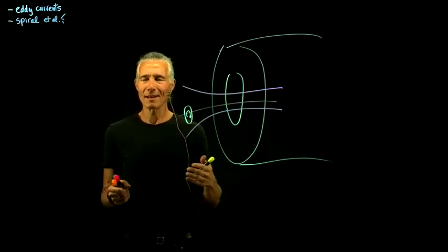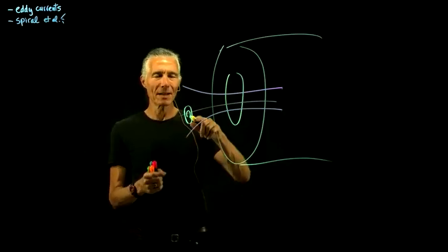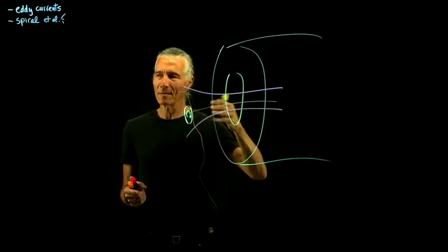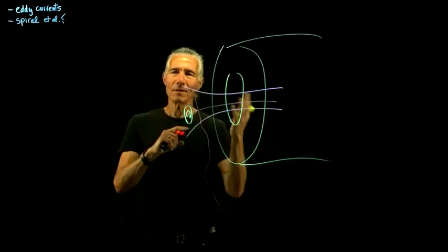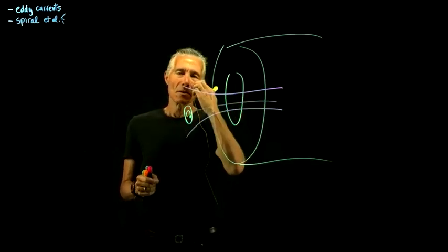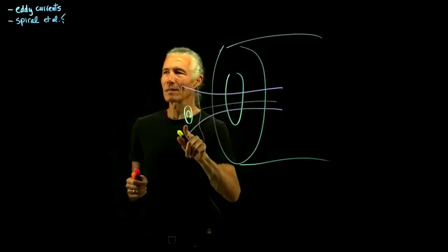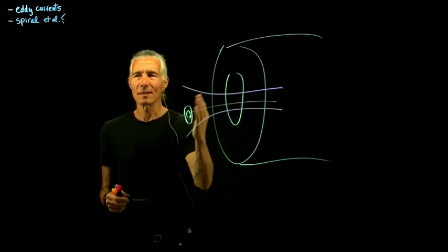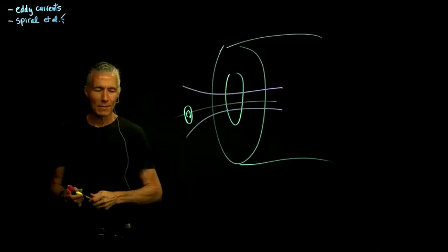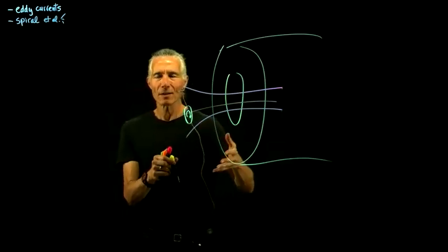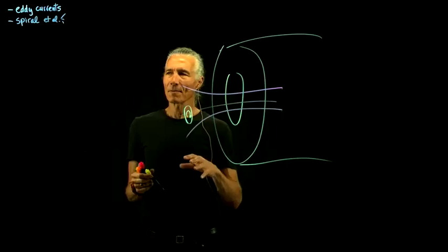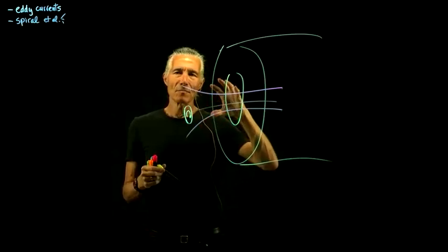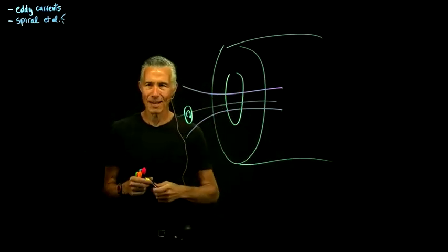It weighs like 10 tons, literally tons of metal, and the gradient coils are changing the magnetic field, moving magnetic field lines around through the charges in the metal. It's the same situation as here, except in reverse: you're moving the magnetic fields instead of moving the charges. So whenever you change the gradient coils, it causes all these currents to slosh around in the actual metal of the magnet, of which there is a lot.